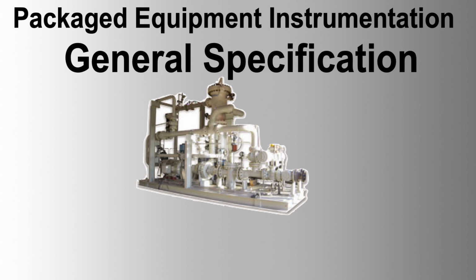Temperature. Thermowells: installed in flanged thermowells designed according to BS 2765 with materials as per process conditions, and should meet hydrostatic testing conditions. Wake frequency and stress calculations should be provided according to ASME PTC 19.3. Temperature gauges: bimetallic type with rigid stem suitable for mounting in flanged thermowell, 4.5-inch diameter dials and aluminum cases. Temperature transmitters: PT100 RTD for ranges between -200°C and +400°C with integral temperature elements. Remote transmitters should be used in cases of high vibration or poor access with IP66 and Ex d or Ex e certification.